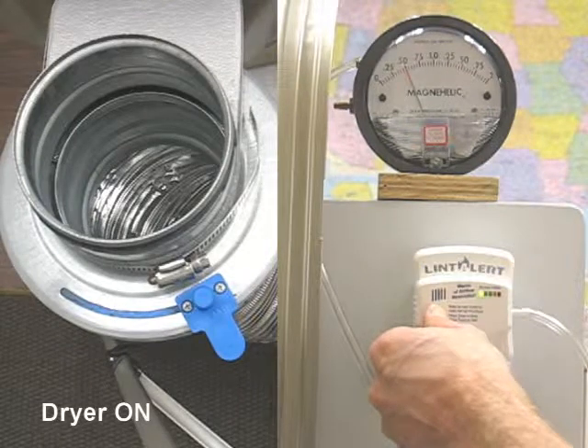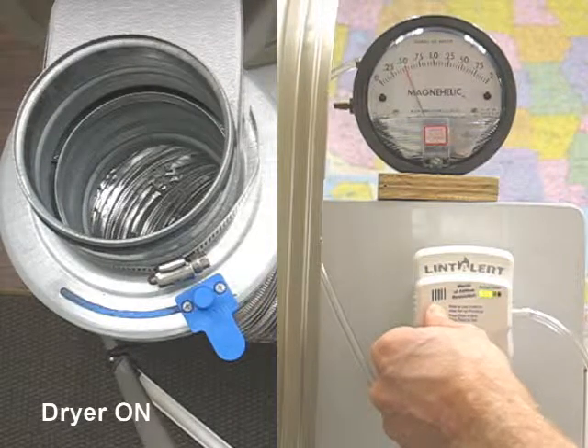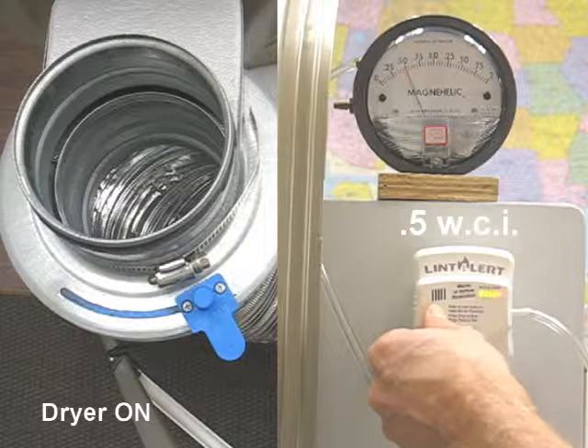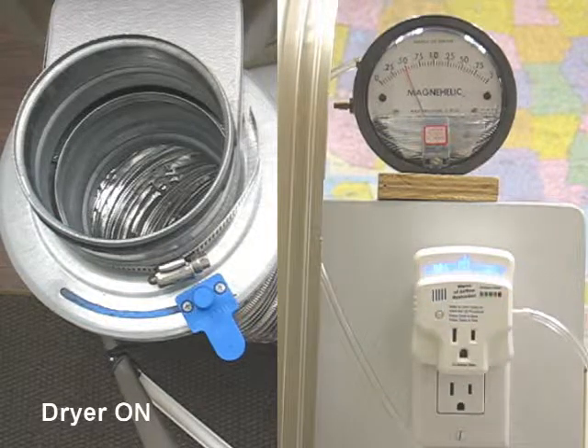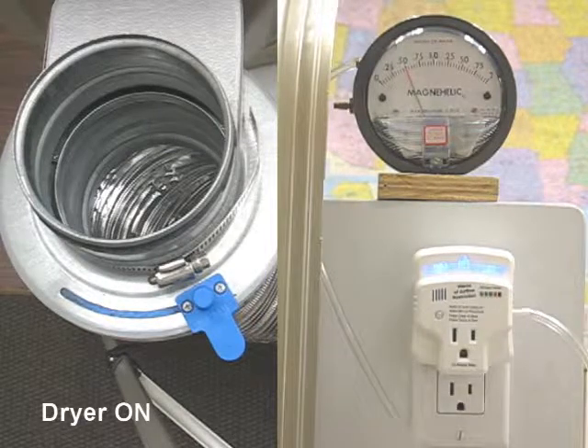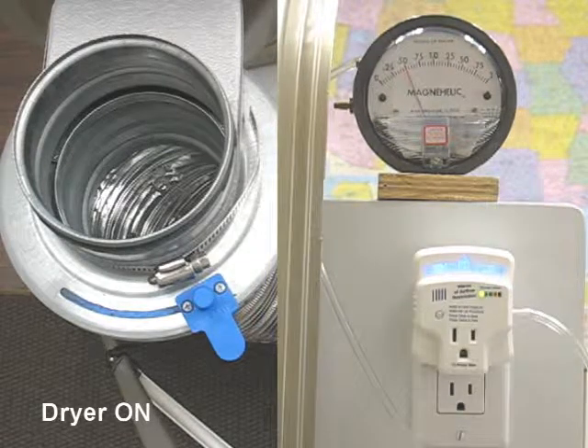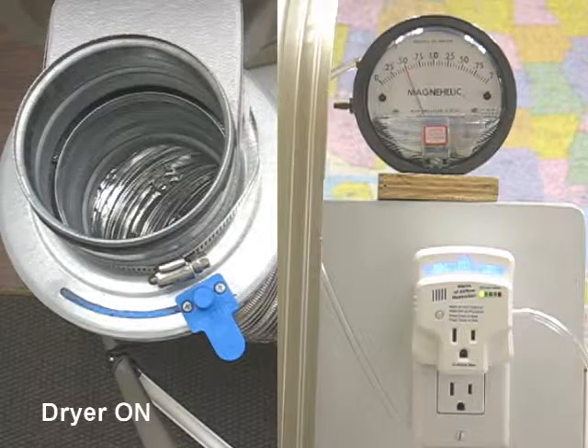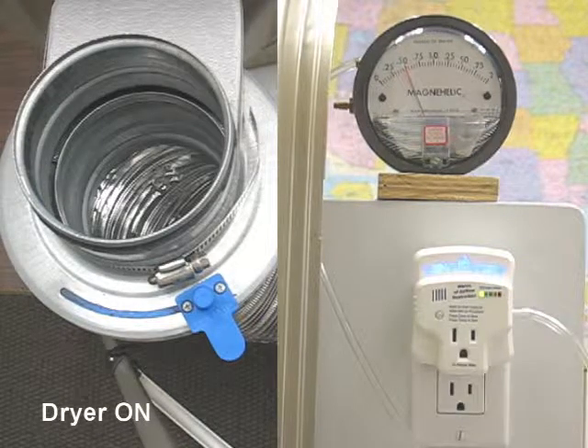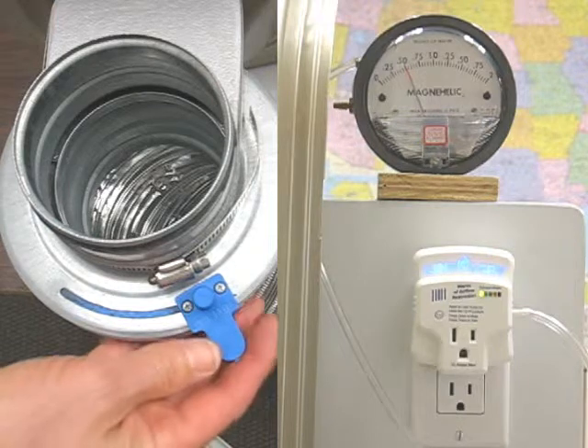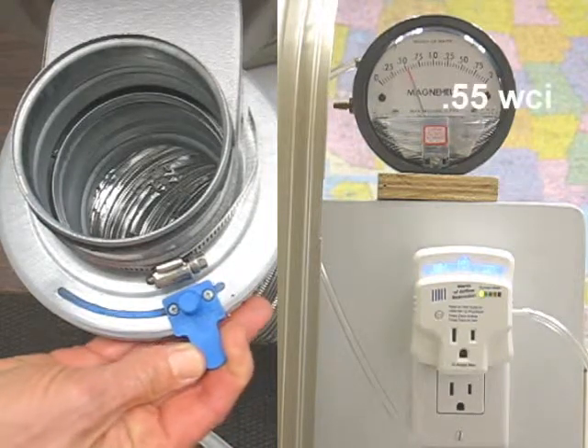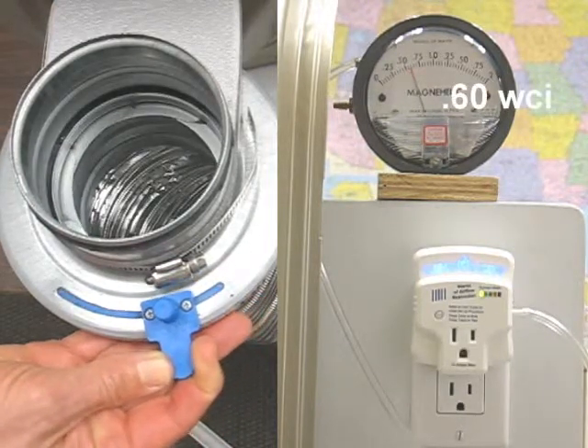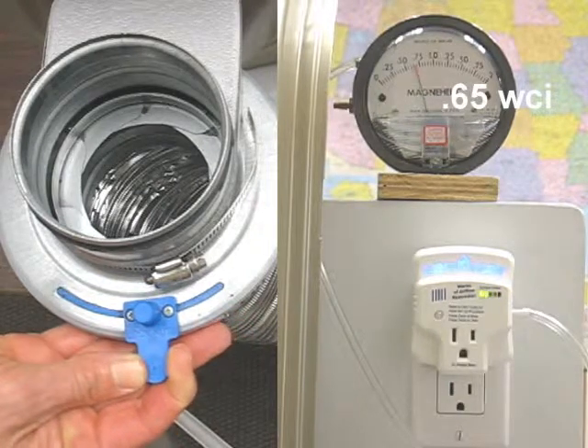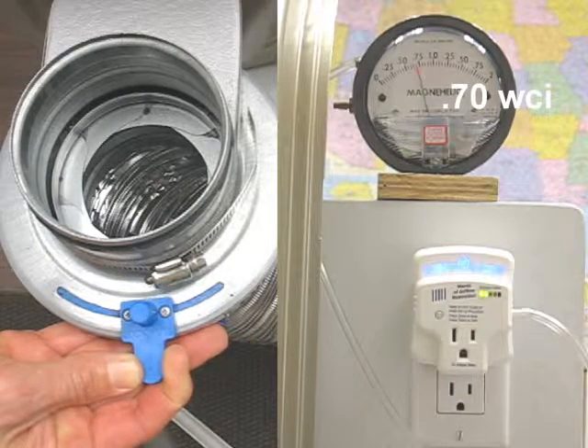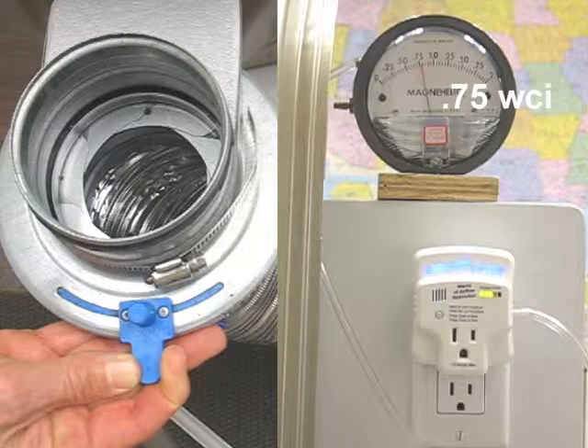In this example, we successfully captured a clean value pressure of 0.5 water column inch, a pretty good mid-range or typical level. And after a slight pause, we observe the first green LED is illuminated, indicating to us that the dryer is on and that about the same amount of back pressure exists as when we initially calibrated. As I choke the airflow by slowly closing the aperture, you'll observe in unison that as the gauge needle rises, so does the blockage indicator light bar.